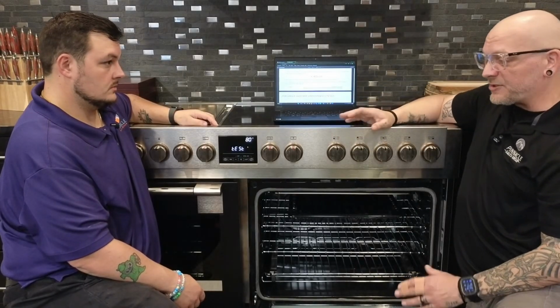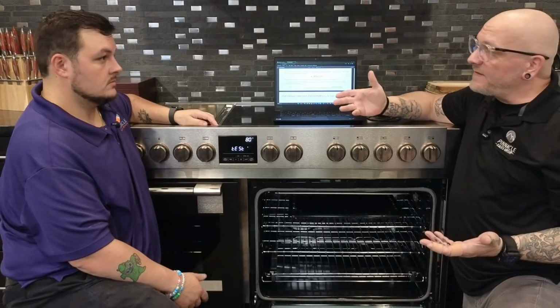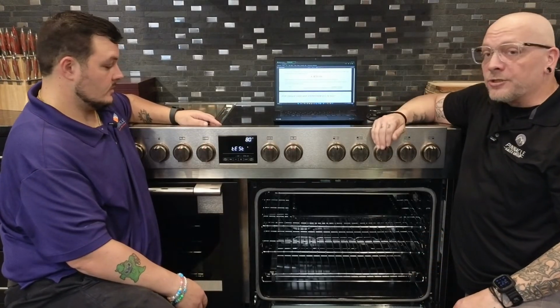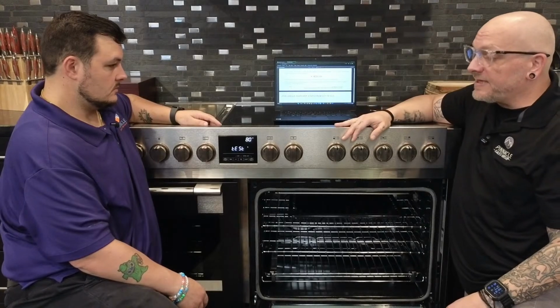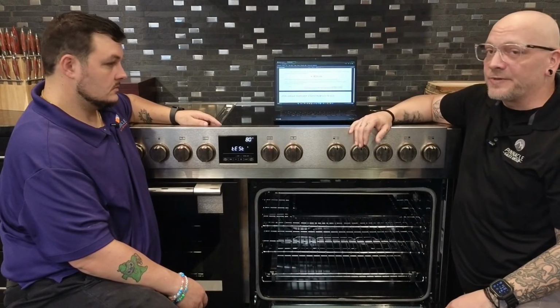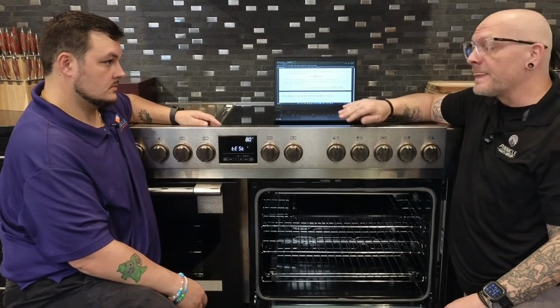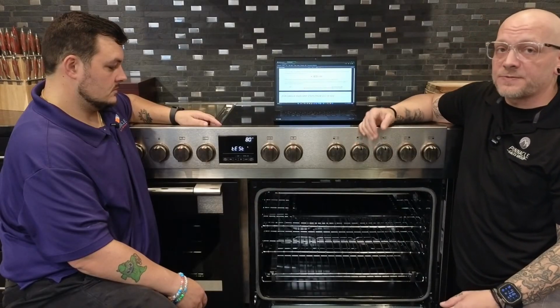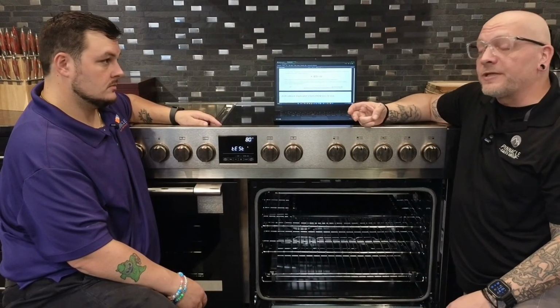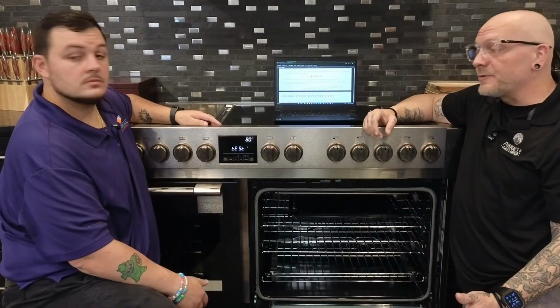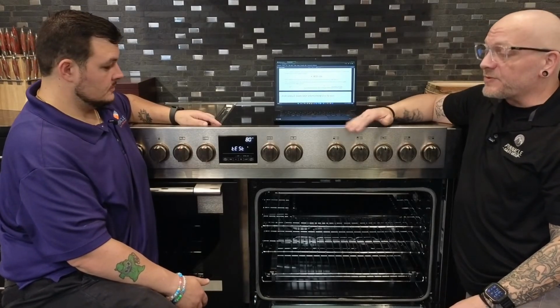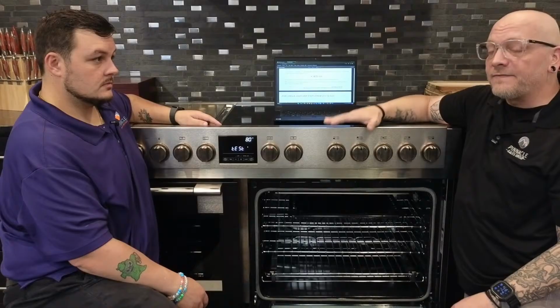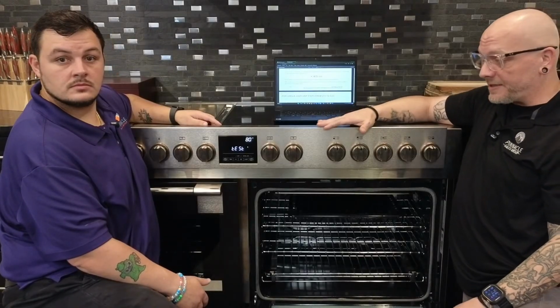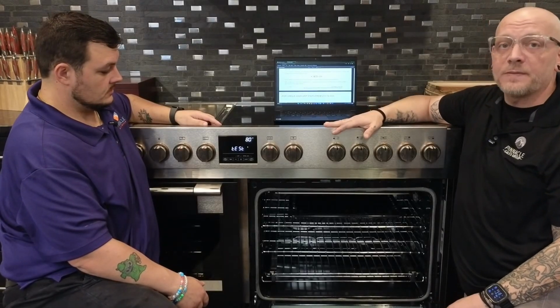So without getting it extremely warm - it's about 75 degrees in here right now - that's good, a good test for us to see as technicians. If this was reading 100 degrees, or a really high or really low number, that may be a direction to go toward if the customer's undercooking, overcooking, or burning the outsides of foods - check their preheat times. Obviously there's more to get into, but this is a great visual test for technicians and customers to see that, hey, the temp probe is probably reading okay.